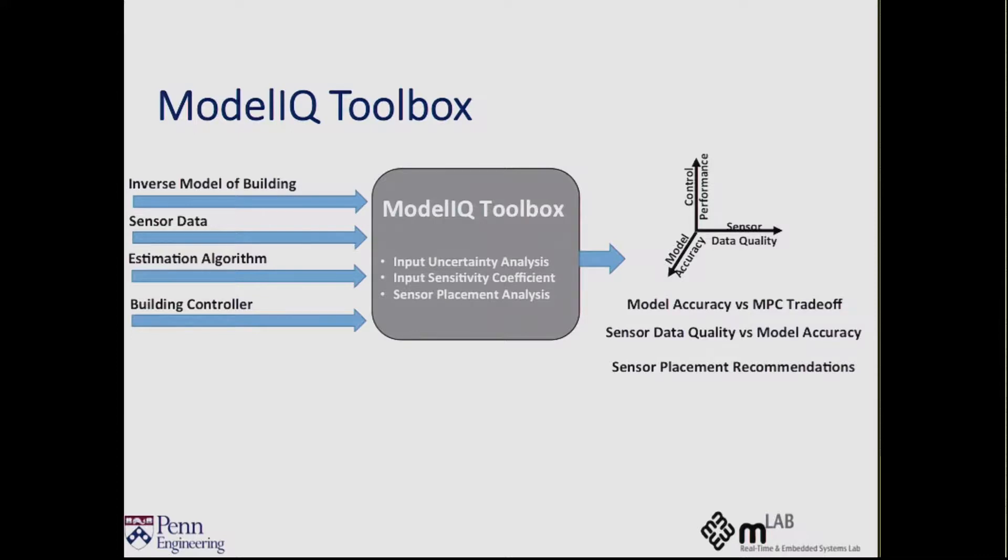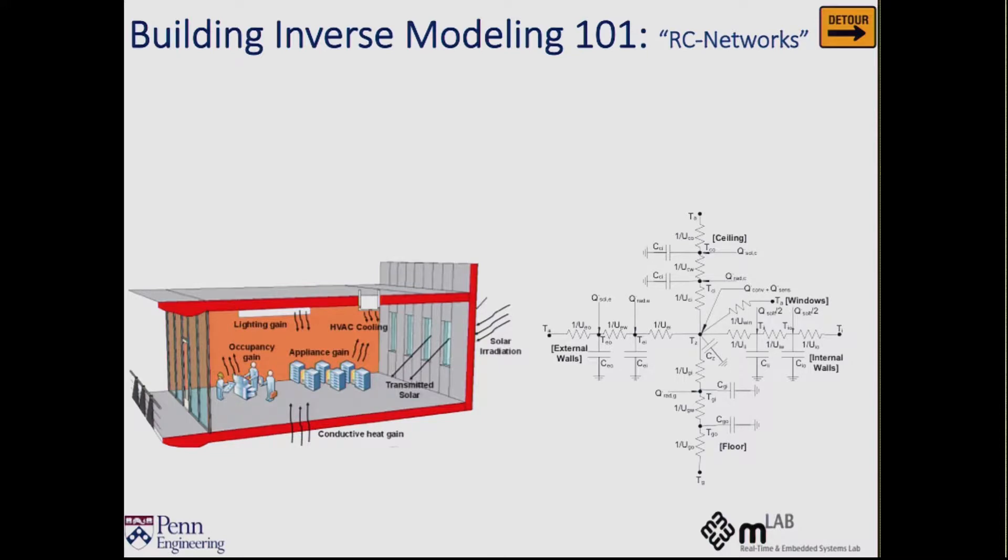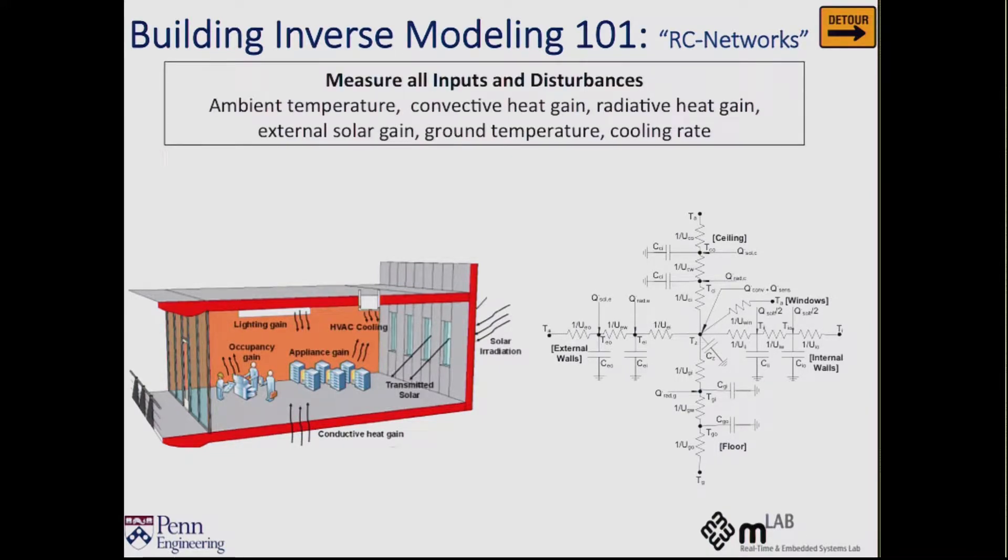But to understand what it does underneath the hood, I will give you the quickest possible crash course on how do you model a building dynamically. So say I have to learn the dynamical model of this room, the first thing I would do is measure all possible disturbances of this room. So there's a chicken-and-egg problem here. I want to avoid using additional sensors, but to begin with, I need to measure some disturbances. So the way out is using these virtual sensing techniques or using some low-cost temporary deployment to establish this initial model. But the idea is you measure these disturbances, and this kind of a modeling is called gray box RC modeling for buildings.